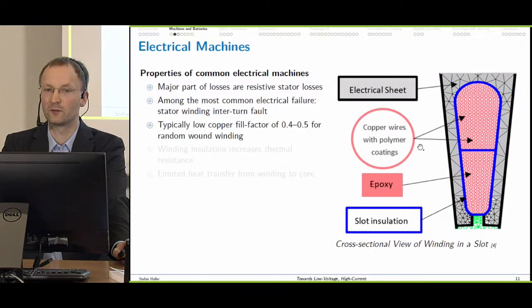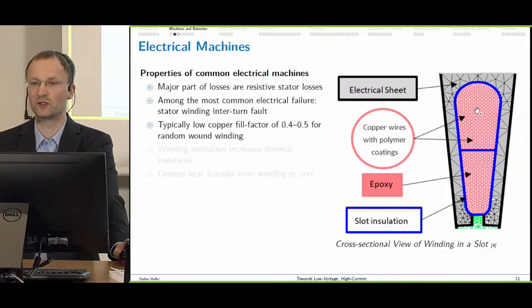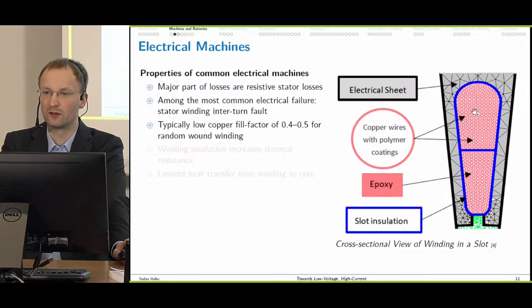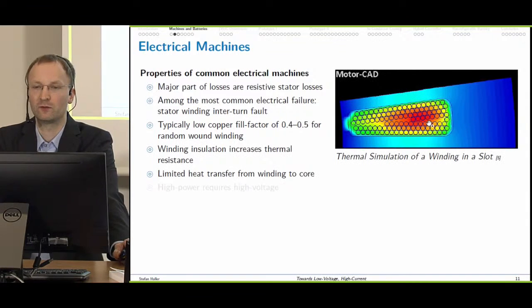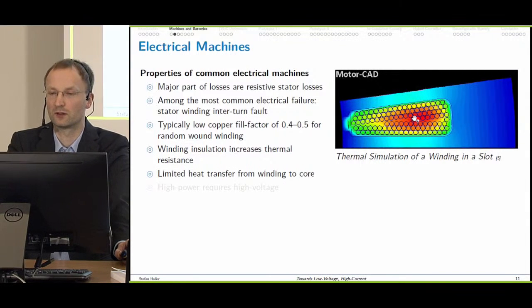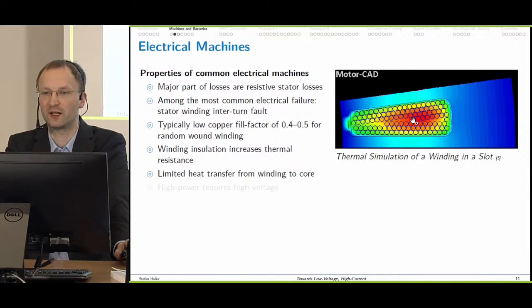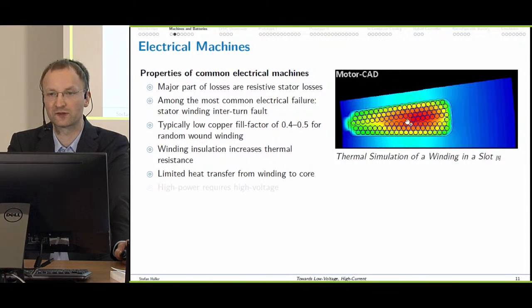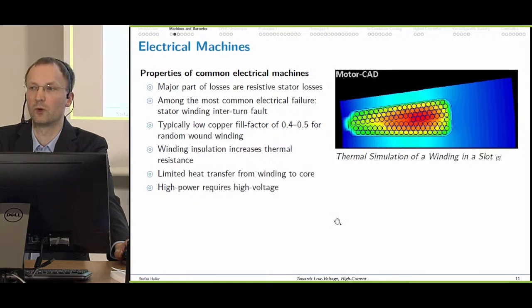Machines with a random wound winding have a typically very low copper fill factor of 0.4 to 0.5. Here on the right side in the figure we see the wires with the isolation coating. It's usually 2 layers of paint, and epoxy resin filling the voids to increase the thermal conductivity and mechanical stability. Speaking about thermal conductivity, if we have many wires in a slot, the design needs to account for that, and the hotspot is usually in the center of the coil, and the heat needs to be transferred to the stator to be finally extracted from the machine. So heat transfer on this winding type is limited. And high power machines usually require high voltage. In industry, having high power machines with 1000 volt and more is common practice.